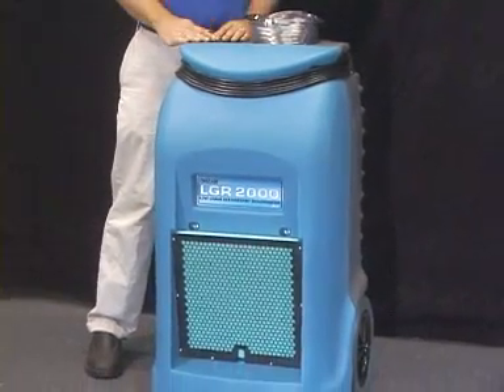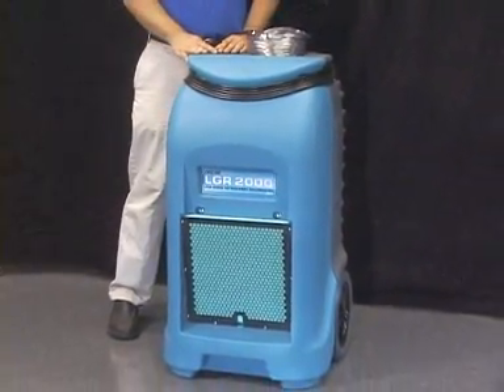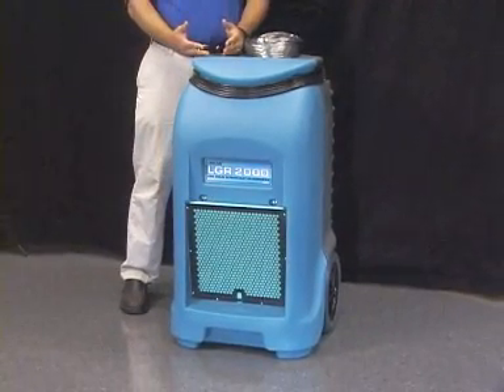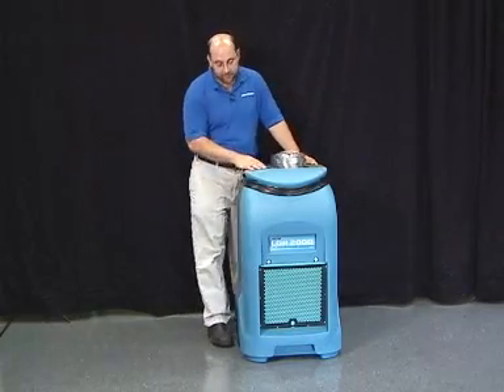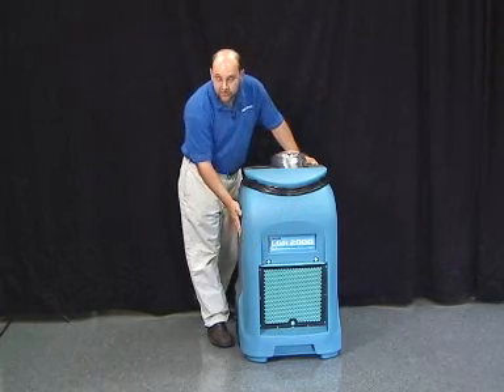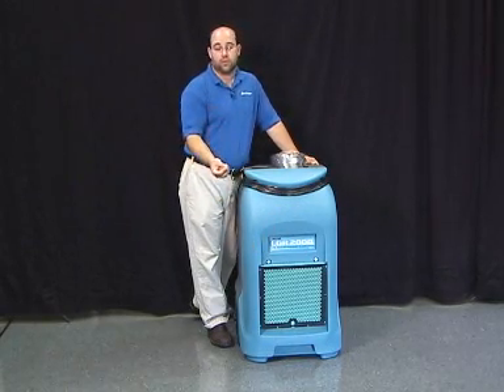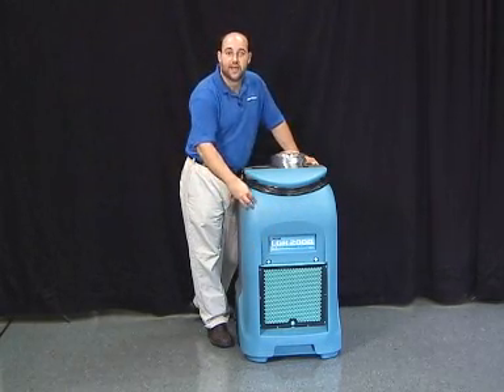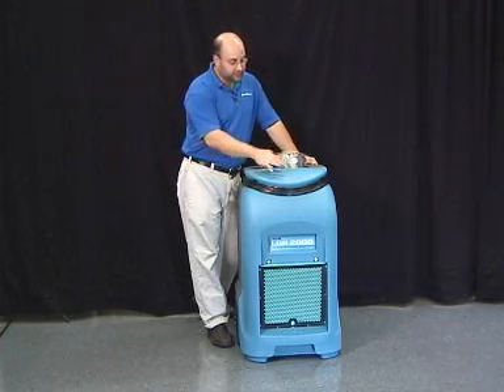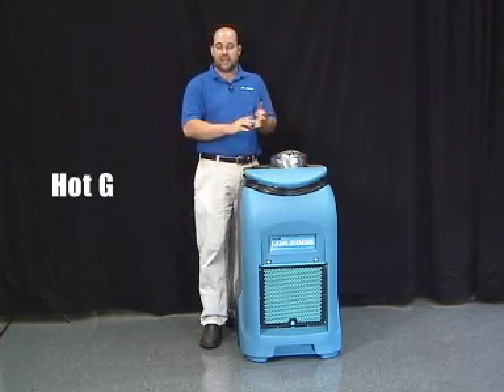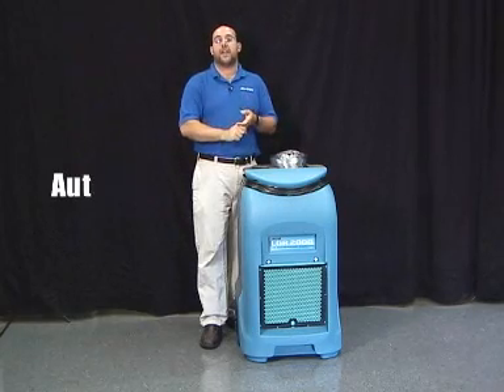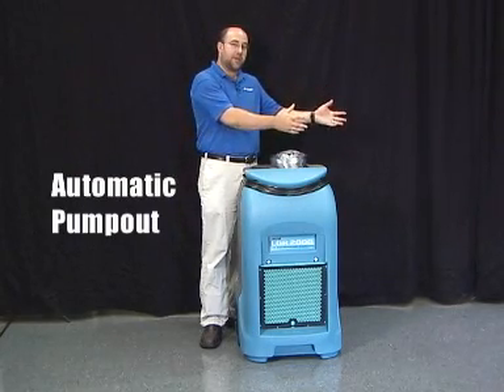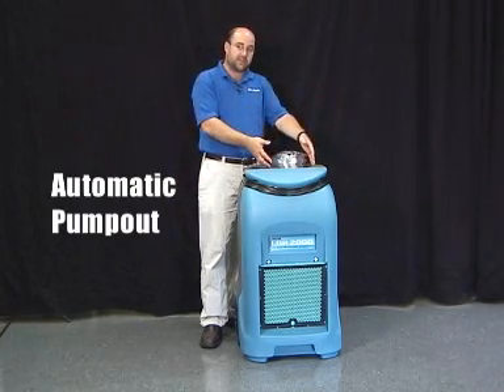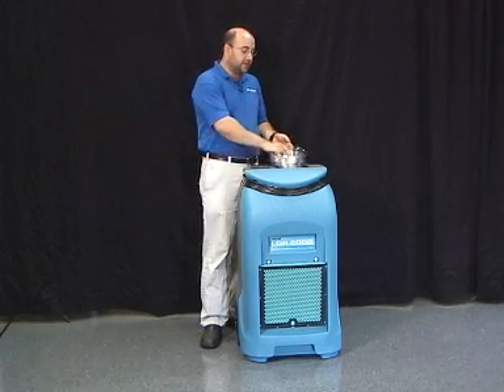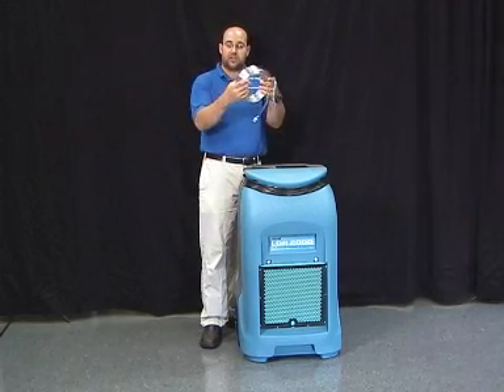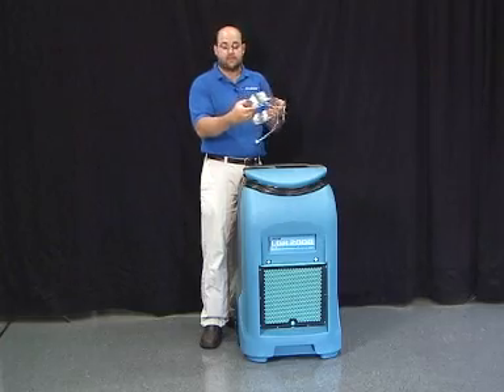The LGR 2000 is also treated with an antimicrobial at the time of injection molding. That antimicrobial basically creates a barrier on the shell to avoid any type of fungal growth getting into the actual material itself. The LGR 2000 also has a hot gas bypass and has an automatic pump out system that will automatically dispense the water from the pump system to a drain source, and it's usually done through this drain hose, which comes standard with the LGR 2000.